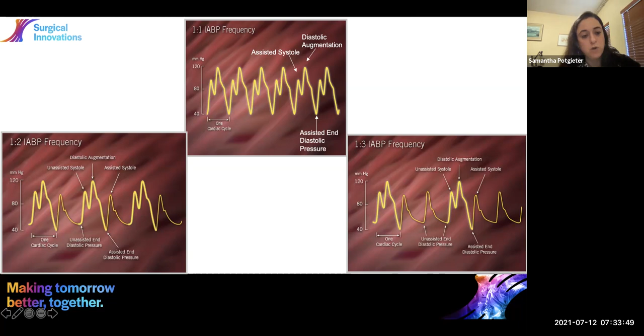Right, so if we go back here and you're looking at your balloon, you need to be able to interpret the pressure waveform that the balloon shows on the pump console. And this is the balloon itself. It's not on the A line. It's on the balloon itself. It's on the console of the pump.